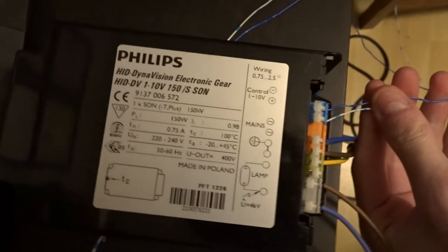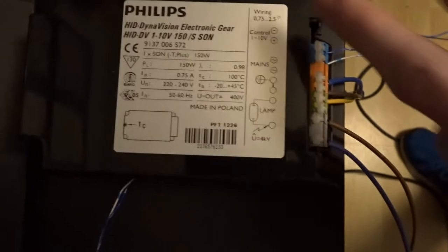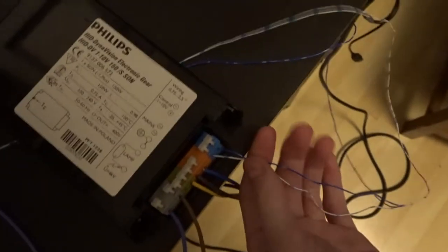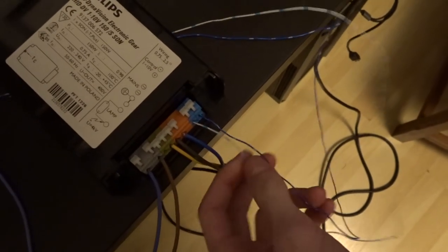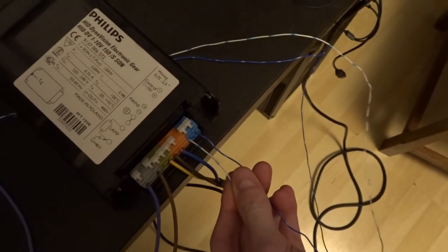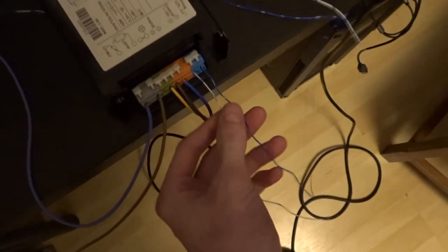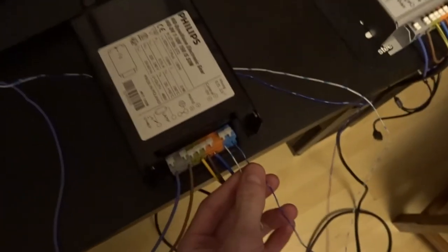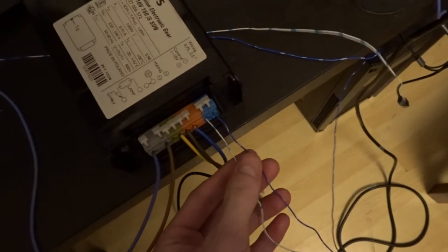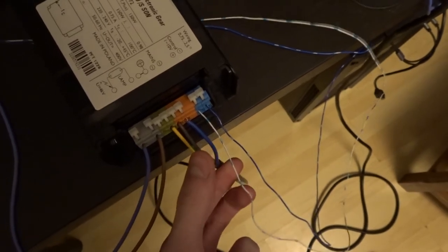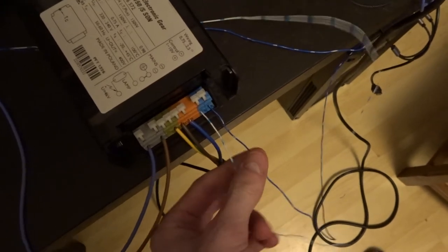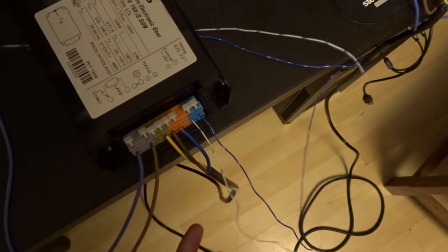These are very cool because this one here is a 1-10 volt dimmable, so it takes a 1-10 volt control line. The way that works is essentially when you connect these two together and you short them out, it will dim all the way down to the lowest but maintainable light level. When you open them up it will go as bright as it goes and you can sort of vary in between. You can pulse or modulate the connection between the two.